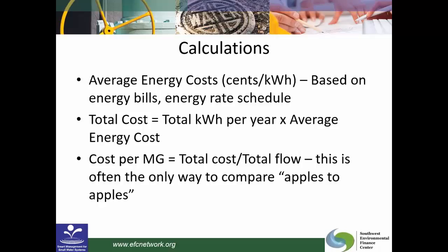And this information becomes pretty valuable in looking at how you're running your plant, why you're running which pump you're running, those kinds of things. And then the last thing that we want to do is take that total cost and divide it by the flow that it's producing. This is about the only way to compare apples to apples. So if you want to see what each pump is costing you, because we run them differently and we have different flows that go through them, dividing it by the total flow allows us to see what it actually costs per million gallons.